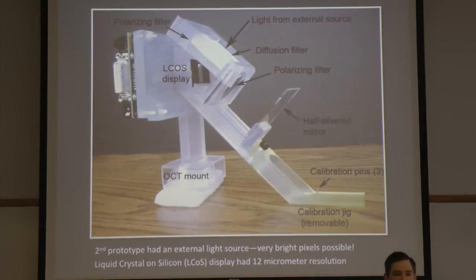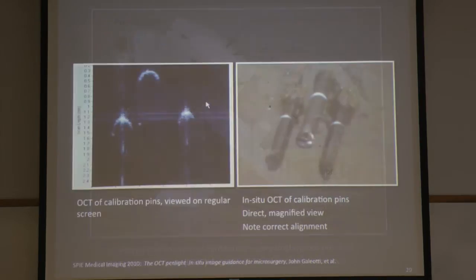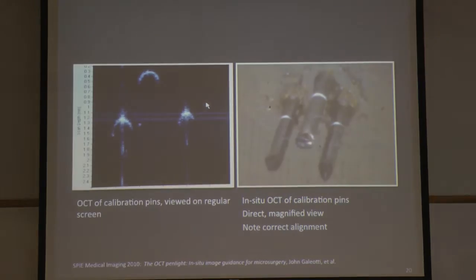I led a senior design team to produce a new prototype which borrowed technology from rear projection televisions designed to have external light sources using a liquid crystal on silicon microdisplay. And using this approach, we were able to produce a very small, very bright, high-resolution image. In this case, you can see 3 very tiny metal pins here, the OCT image of the 3 of them. It has specularities happening at the cross-section, but you can see the 3 simple curves. And looking through the calibrated system, you can see the curves of the OCT are perfectly aligned with the 3 pins we're looking at, demonstrating that the system is calibrated, and they're able to see it correctly. I think the resolution of this display was 12 micron pixels, I believe, and could easily adjust the brightness to whatever magnification we needed.